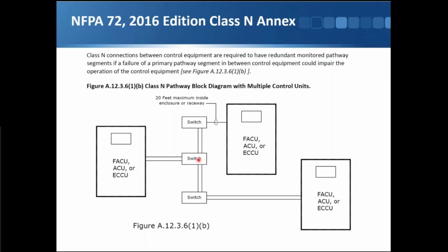On that note, even going back to class A and B, we added C, D, and E, and now we have class N. In my opinion, it would be appropriate for engineers to sometimes specify that this part we want to be class A, and then, for other reasons, because of the physical environment, we'll allow this other area to be class B, or maybe even class C, where they would report a loss of communication to the other points that they're supposed to monitor, but we don't really specify how they're doing it.